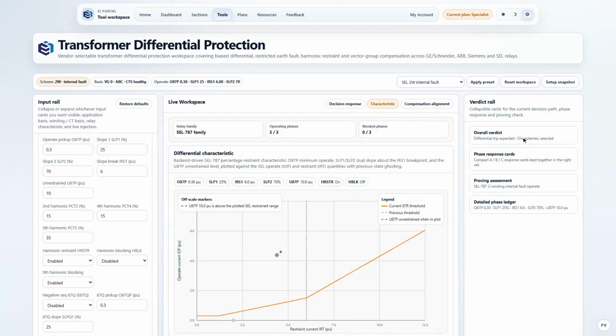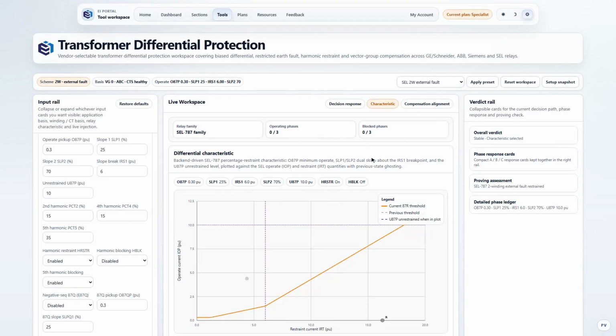Next, the external fault, and this is where schemes get found out. Heavy through current pushes restraint to 16.26, well past the slope break, so the threshold rides the steep second slope up to 8.68. The compensated currents still cancel, and even a real CT error spilling current would need to beat that raised threshold. Internal trips, external restraints. The dual slope is the whole job.